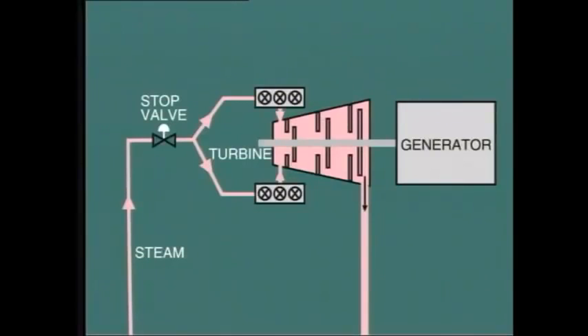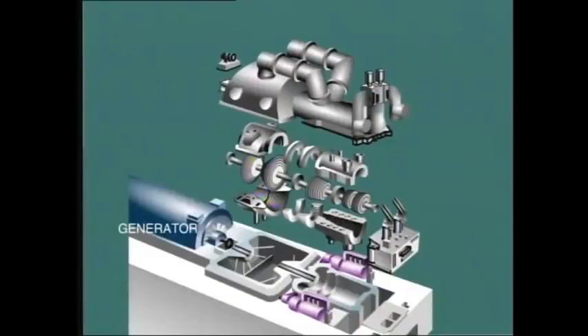In this particular machine, steam from the stop valve is fed into steam chests located on either side of the turbine. The turbine admission valves are located in each steam chest to control the flow of steam into the turbine. The turbine rotor is directly coupled to the generator rotor to transfer the mechanical energy produced in the turbine to the generator, where it is converted into electrical energy.